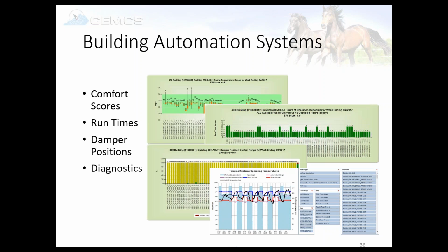The next one down looks at just run times. So you can grade your schedules. The equipment that is scheduled longer sticks out like a sore thumb, as you can see there. We've got a lot of 10-hour, 12-hour, and then you jump up to maybe a 16-hour operating load per day. The next graph down shows damper positions. It's got a little bit of green on some of those bars, a little bit of red, but mostly yellow. That means the valves or the dampers are modulating to maintain space temperature. We would really want to look at one if it was pegged all the time. That bar would be red, and that means it's having trouble maintaining the set point.